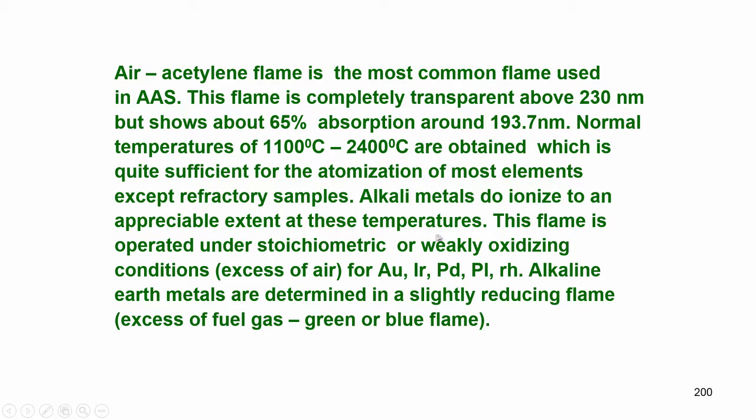Continuing this discussion, the air acetylene flame is operated under stoichiometric or weakly oxidizing conditions, that means excess air, for gold, iridium, palladium, platinum and rhodium. Alkaline earth metals are determined in a slightly reducing flame, that is excess of fuel gas, a green or blue flame, because the temperatures are lower than the optimum, but quite sufficient for alkaline earth metals.